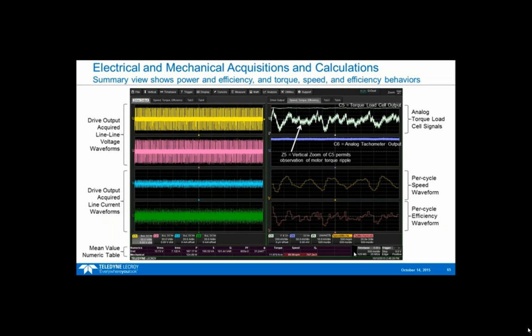So this is the view right here - I'm looking at the drive output on the left. Again, the customer chose to use the 2-wattmeter method here, using 2 voltage signals and 2 current signals. If you wonder why one of these current signals looks so much noisier than the other, they were using 2 different types of sensors, not the same kind. They were just trying to find out if they could do that with our product, which is why they look so different.